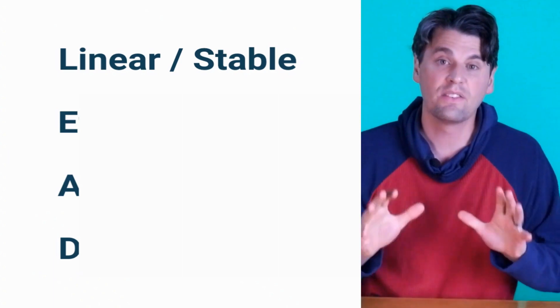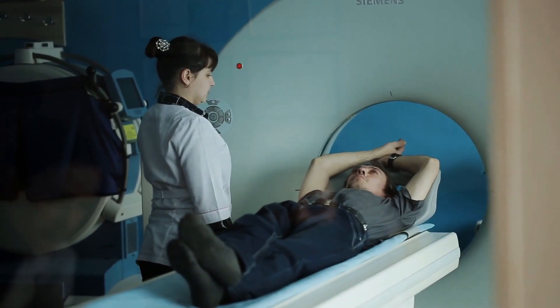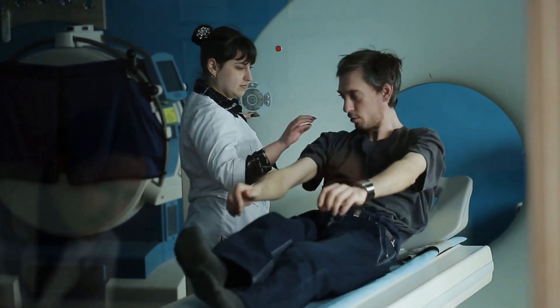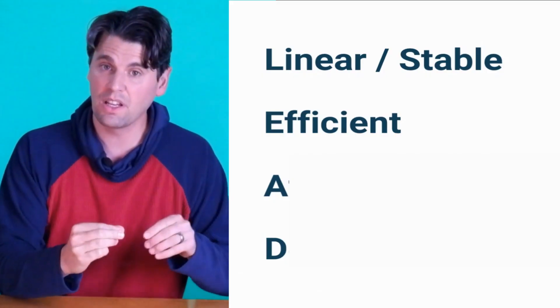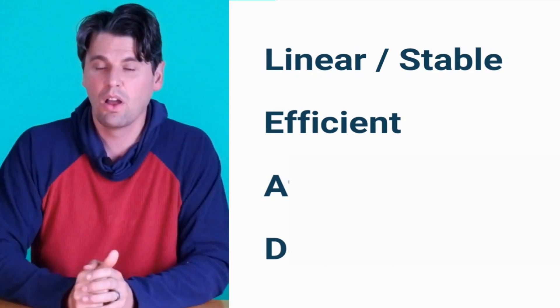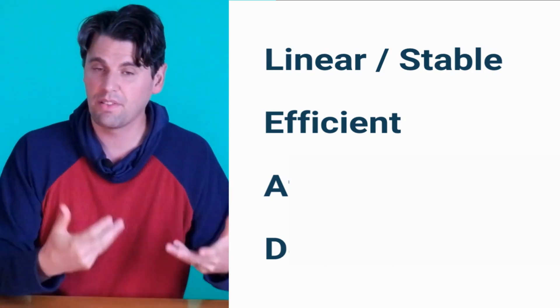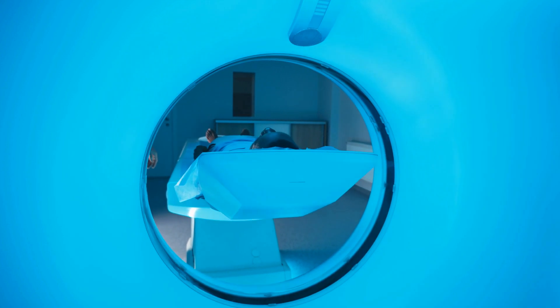We also want the detector to be stable. CT is used as bread-and-butter imaging and we want stable, dependable imaging over time. E is for efficient — we'd like the system to efficiently convert x-ray energy into a measured signal. If the system is relatively inefficient, there's dose going through the patient that isn't being measured on our detector.